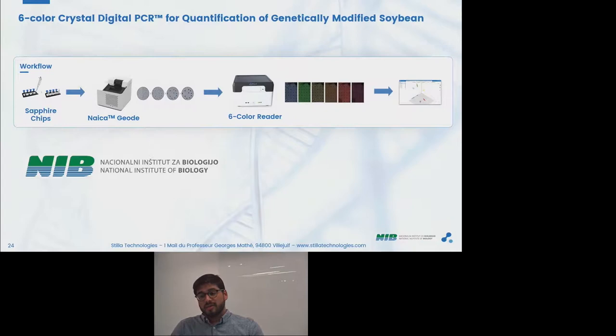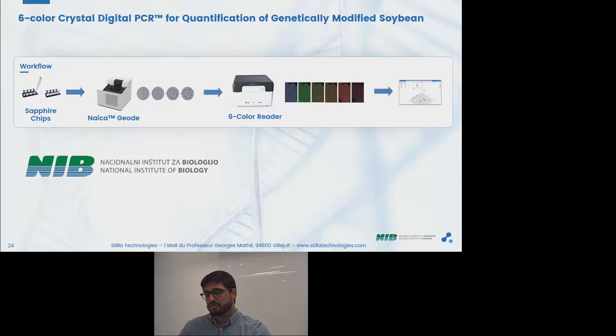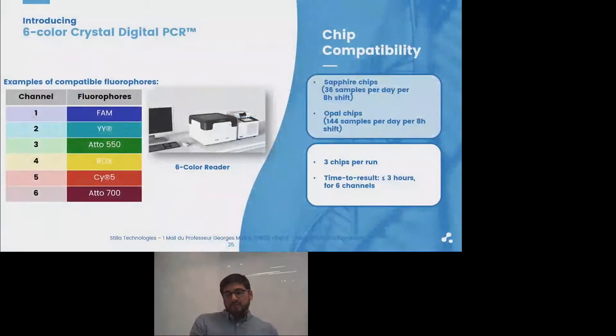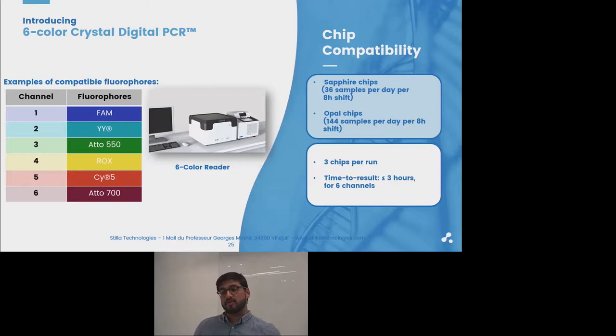With the six-color reader, the setup is identical to the three-color workflow: one pipetting step to load the Sapphire chips, then the Naica geode to perform the partitioning and thermal cycling. The difference is now in the number of colors the reader can detect, doubled from three to six. We still have our fully integrated software to analyze results in an easy and intuitive manner. The six-color Crystal Digital PCR can use a wide range of fluorophores as in qPCR multiplexing — the listed fluorophores are examples of compatible options, though this is not an exhaustive list. The six-color reader is compatible with our Sapphire chips and our soon-to-come Opal chips, allowing you to run up to 36 or 144 samples per day respectively with one geode.